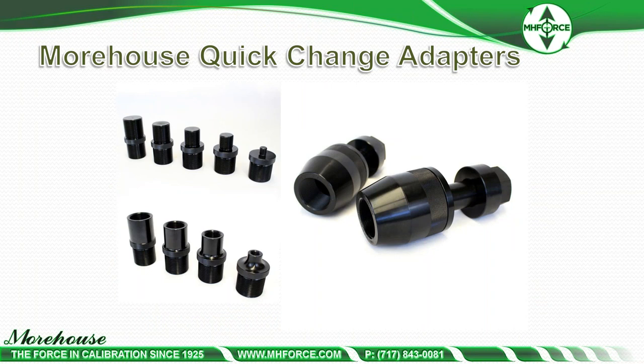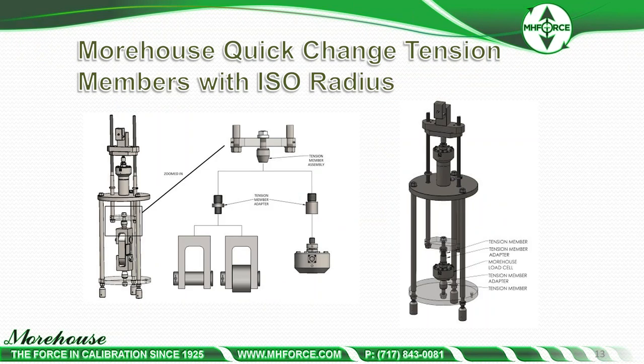Where do you get these adapters? We've made one set of adapters combining ISO 376 and lean manufacturing principles — focusing on quick changeover, quick setup time, and cycle time. On the right are various thread sizes that thread into these adapters. For a tension application, you don't need a ton of adapters — one kit with all the thread sizes needed for your lab is sufficient. On the left is a CAL machine with those same tension adapters with sphericals and clevises to calibrate devices like a Dillon ED2000 or Tractel. Those adapters with sphericals help keep the line of force pure.